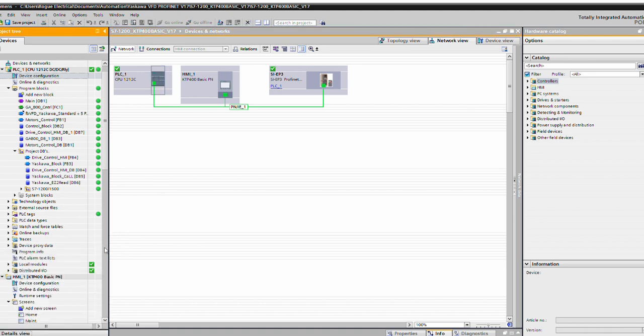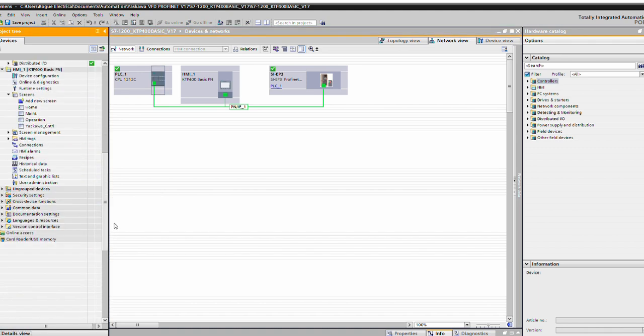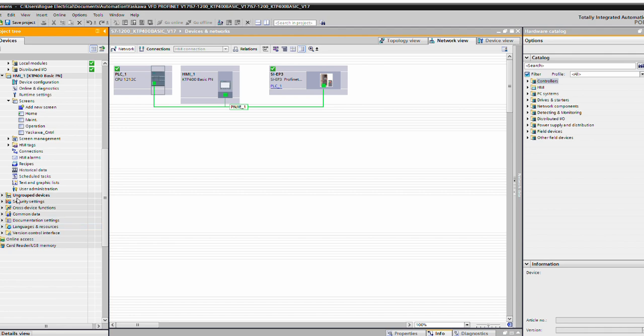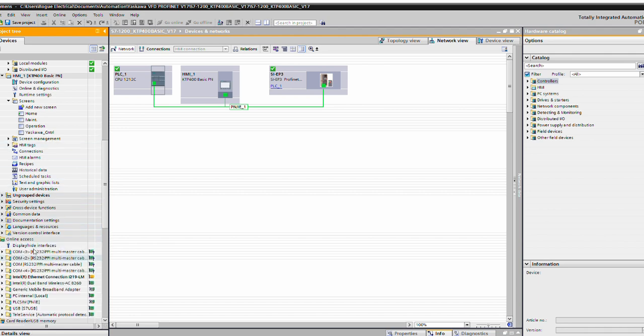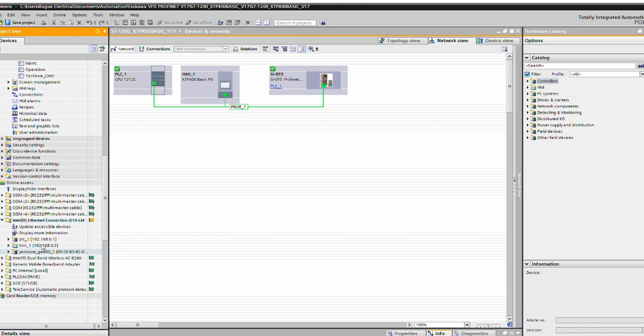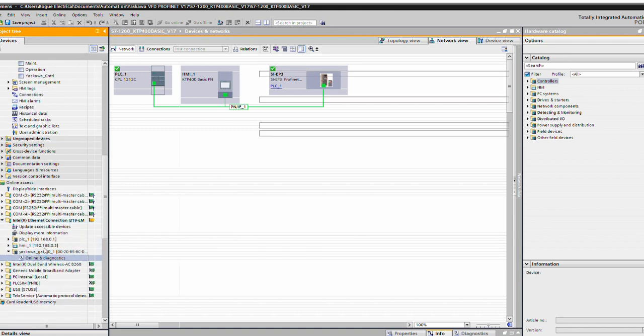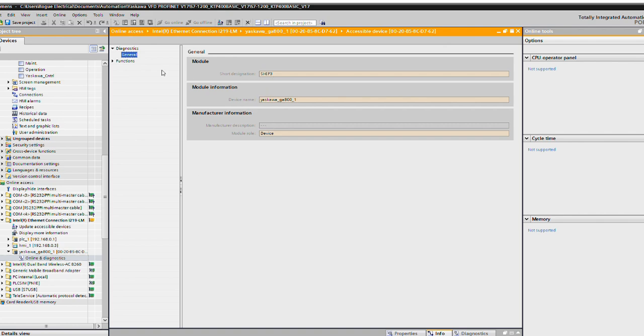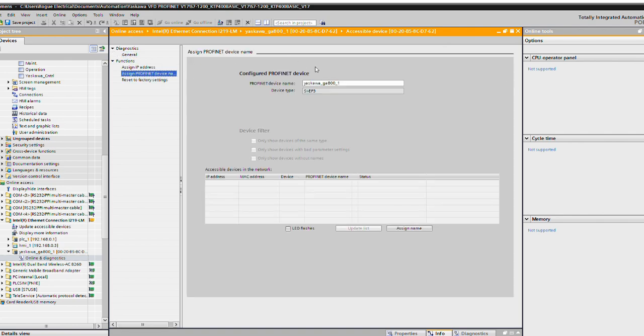Now the way we get this configured is we're gonna have to connect to it through our accessible devices through online access. Go to your card, whatever switch you got going on. Go to online and diagnostics. What you're gonna have to do in order to get this thing talking is you need to assign it a ProfiNet device name. Now all devices that work on ProfiNet require a ProfiNet device name. You could have that IP address locked in the drive and locked in your program, but it's not going to do anything until you give it a ProfiNet device name.